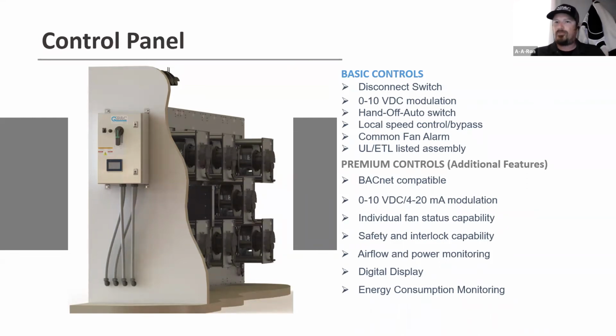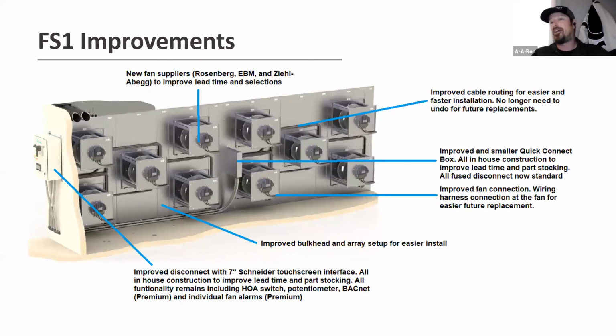You get a common alarm on the basic, and you'll get individual fan alarms on the premium control. So you'll know exactly which fan has failed and what alarm you may get. You'll also have a 7-inch touchscreen digital panel on the outside of the disconnect on the premium controls, which allows you to get energy consumption, airflow monitoring, pressure device monitoring, and everything that gets in there. Fireman controls for interlocks, safety and interlocks, things like that you just don't get on the basic controller. And BACnet. BACnet is on the premium controller. If you want to be able to cut that into a building management system, that's the big key component there.